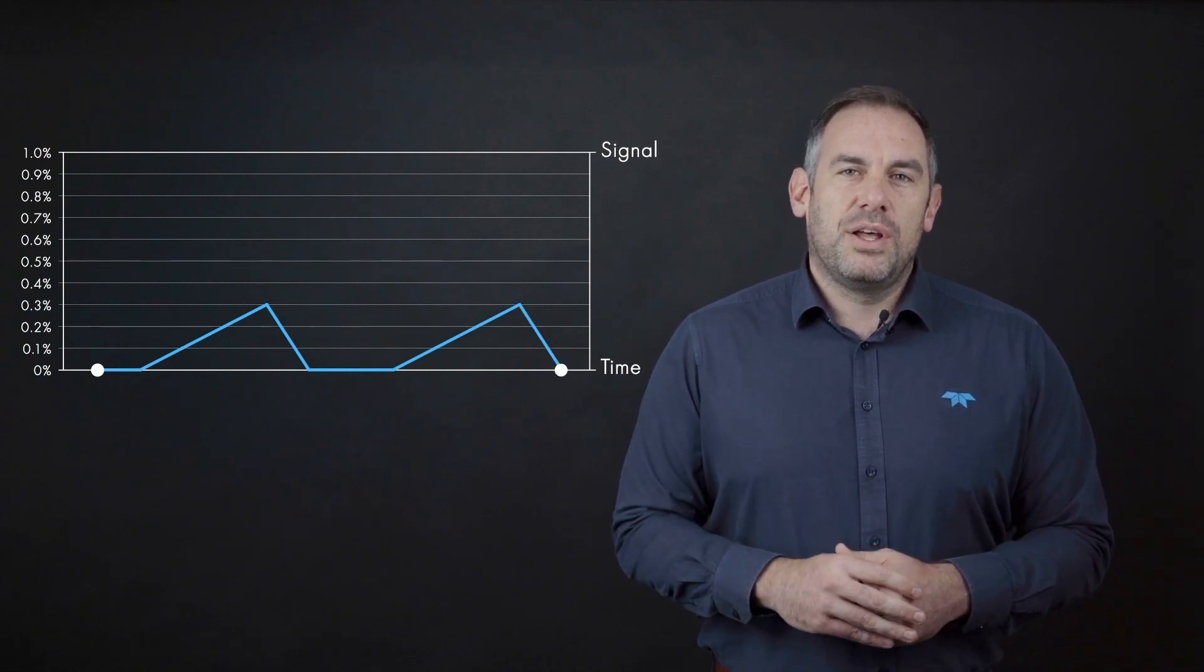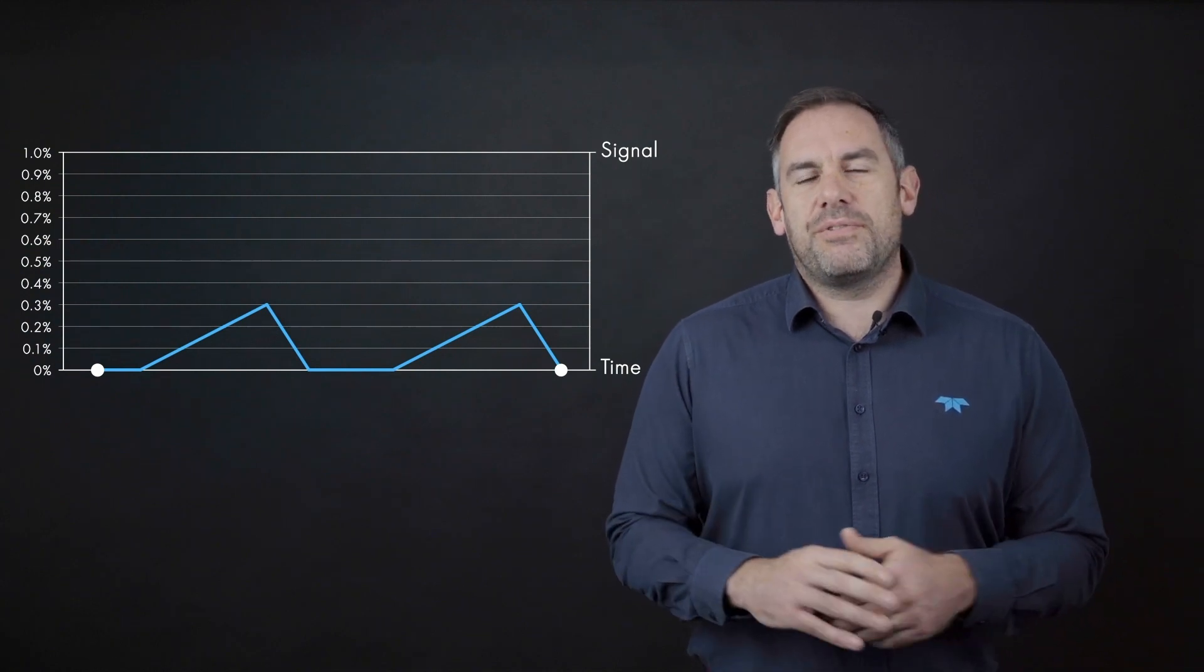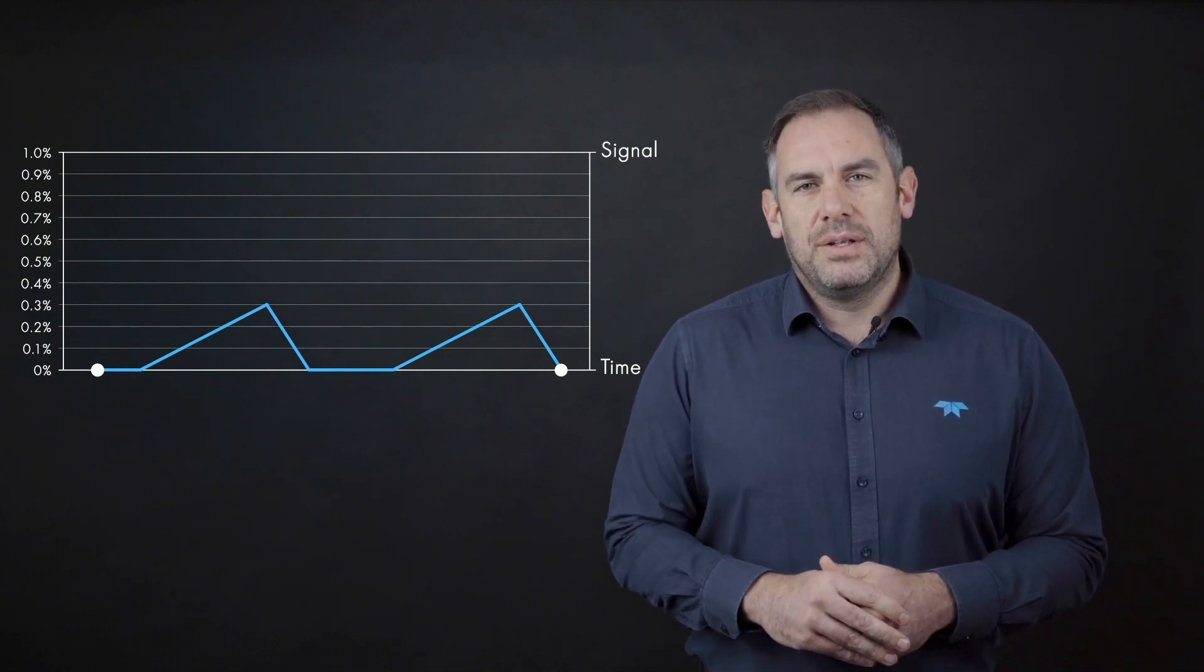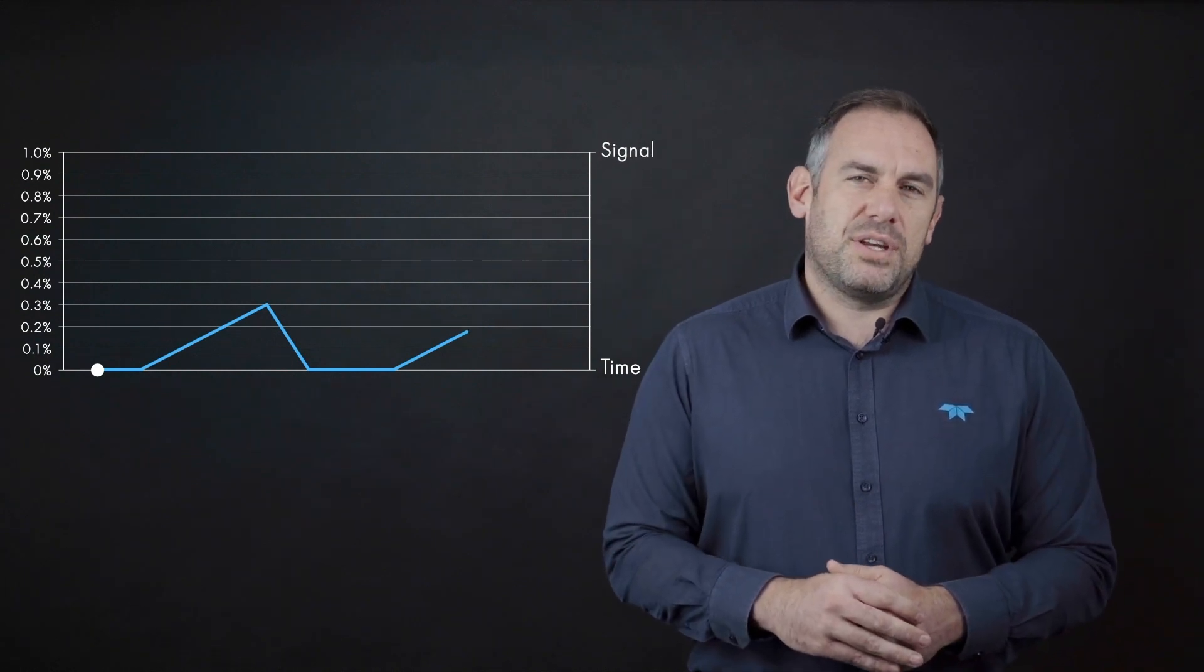In many applications, dirt and contamination will build up over time. But using the information of the absorption of the reference beam, the devices are able to readjust the zero drift that will occur in the presence of contamination. This self re-zeroing of the device will reduce the amount of false alarms and also the frequency of service interventions.